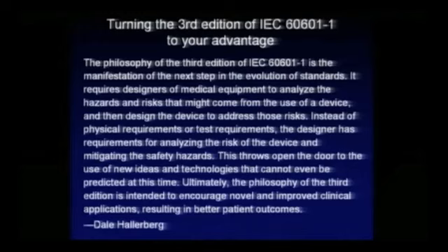It requires designers of medical equipment to analyze the hazards and risks that might come from the use of a device, and then design the device to address those risks. Instead of physical requirements or test requirements, the designer has requirements for analyzing the risk of the device and mitigating the safety hazards. This throws open the door to the use of new ideas and technologies that cannot even be predicted at this time. Ultimately, the philosophy of the third edition is intended to encourage novel and improved clinical applications, resulting in better patient outcomes.